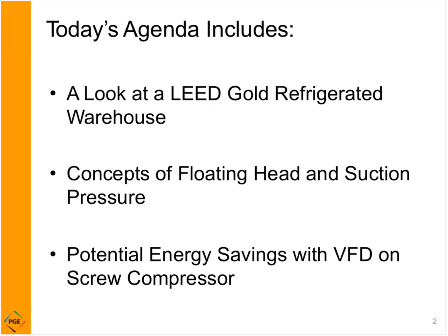Then let's take a closer look at those technologies, primarily floating head and floating suction pressure. These are actively controlling the suction and discharge off of a compressor, and we find substantial savings available from those control strategies. And then the third bullet here, potential energy savings by utilizing variable frequency drive on a screw compressor. Those are some interesting results, and we have some actual measured data to take a look at. So that's what we have in store for you today.